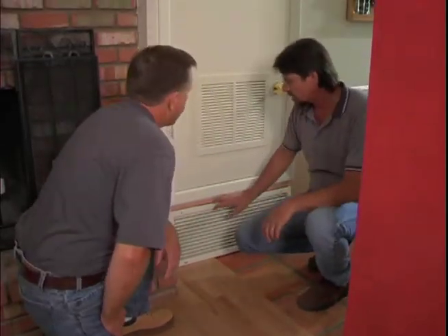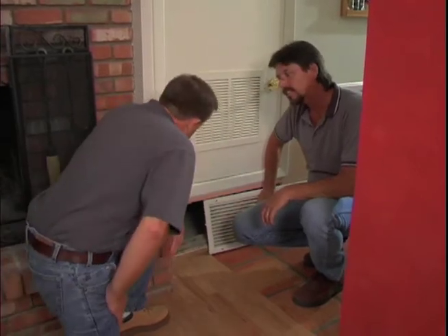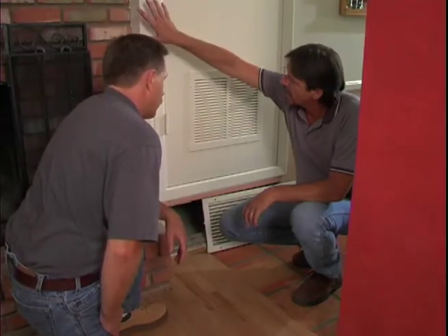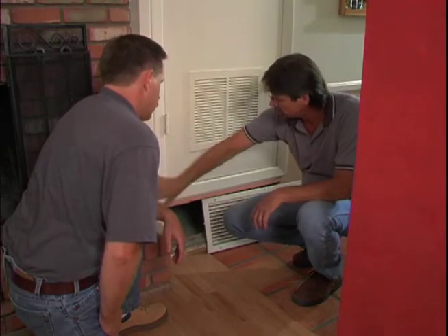Earlier today, I took this return air grill off and found that the return is actually connected to this wall cavity, which is connected to the chimney flue. So what it's doing is when the air handler is running, it's pulling attic air down this wall cavity and into the return itself. So it's connected through the chimney? Well, it's not so connected to the chimney, but it's using the sidewall of this chimney as an air path to get to the attic.